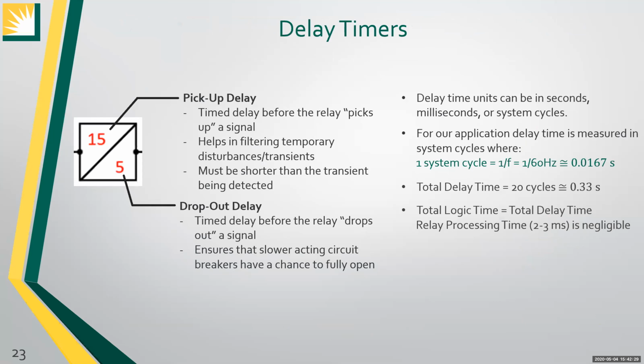As I briefly mentioned when going over the detection logic diagram, delay timers were used as added measures for reliability. There are two types of delay timers in our logic design: pickup delay timers, shown as the top left number in the figure, and dropout delay timers, shown as the bottom right number. The pickup delay waits a set amount of time before picking up any change in the logical signal entering its input, acting as a buffer to help eliminate false positives triggered by temporary disturbances to the distribution system.